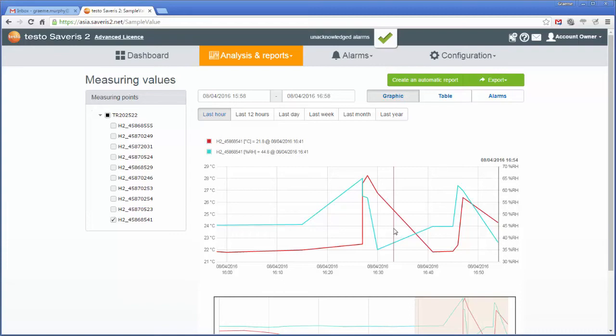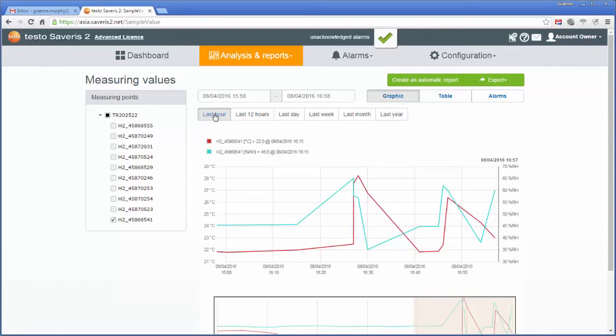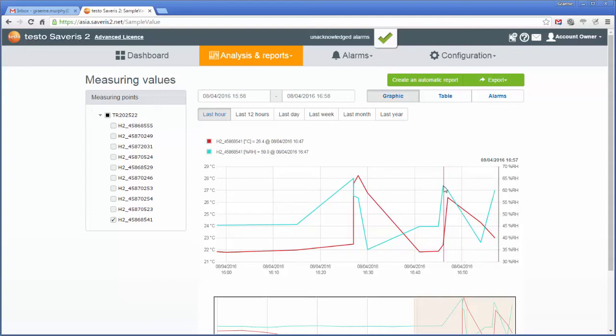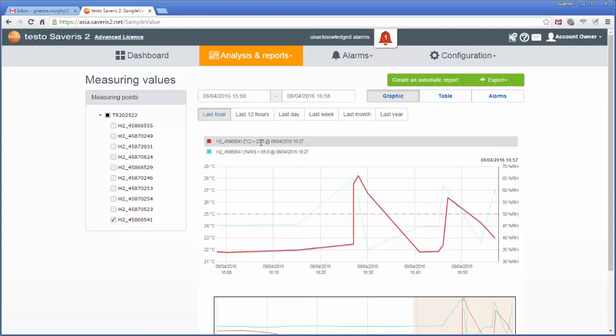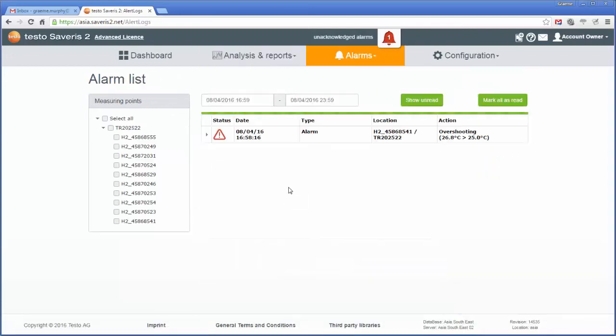Now, I hit the refresh key, so the value will be updated, now I'm going to click on the last hour. Here's our, which one is our temperature, one of these, either one of these is our temperature. There's the humidity, here's our temperature. Now it's showing alarm condition on the particular logger, and it's brought this up here. So we've now got an alarm condition marked, that's gone into overshoot, you can see that, you can see the alarm conditions on the logger, and as well as that.